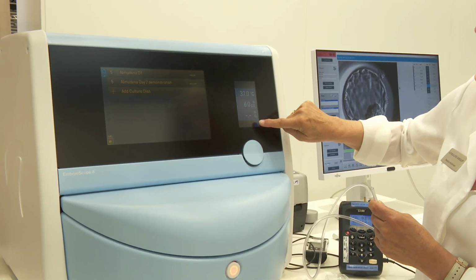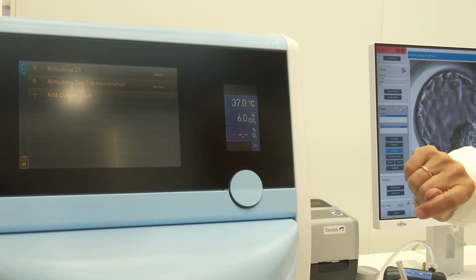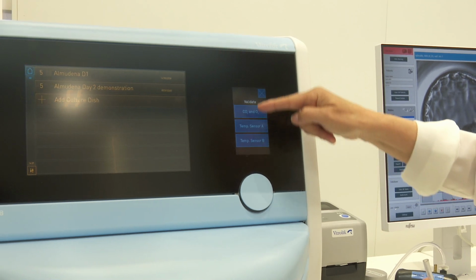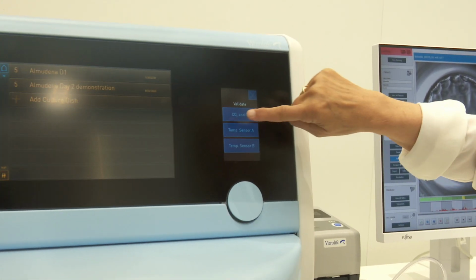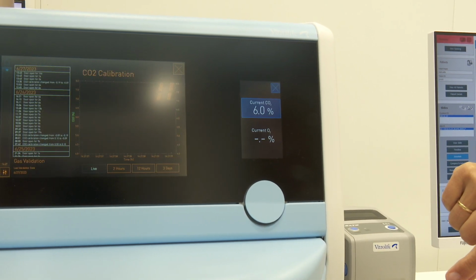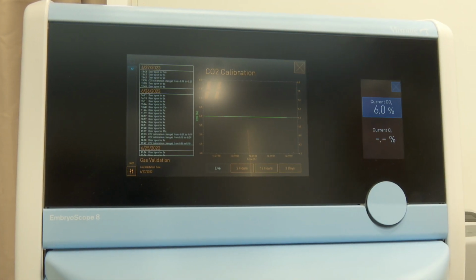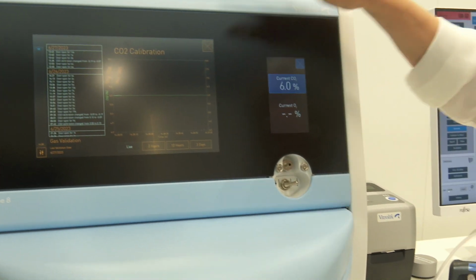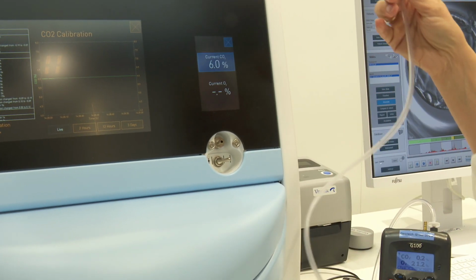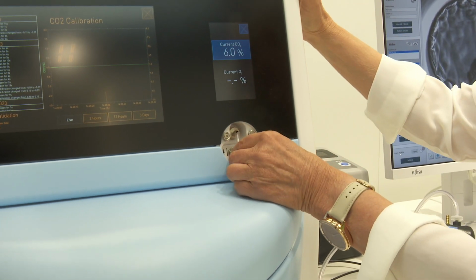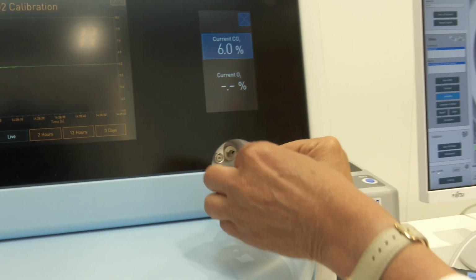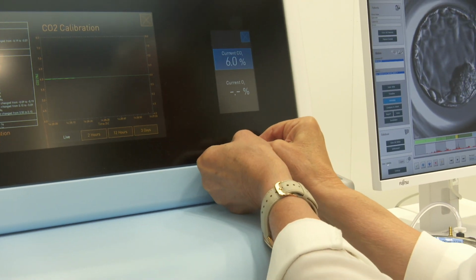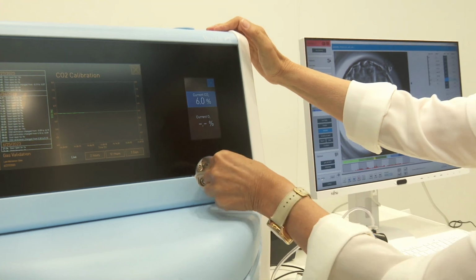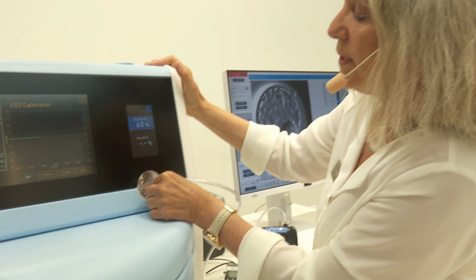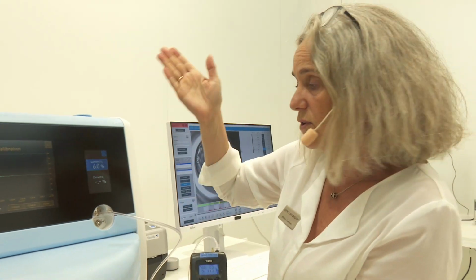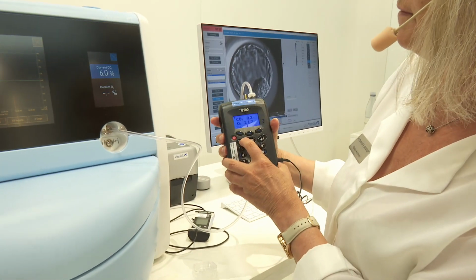So what I do here is I go into the tool where you validate, and you can choose between temperature sensors and the CO2. So we go into gas validation. You can follow the calibration and validation on the screen over here. So from the analyzer, you put the tube on here. It's a little bit difficult with my left hand, so maybe I'm going in front of here. So make sure it's tightly on. And then you put the tap here to the left. That gives you access to the embryo chamber. And then you turn on the fan.